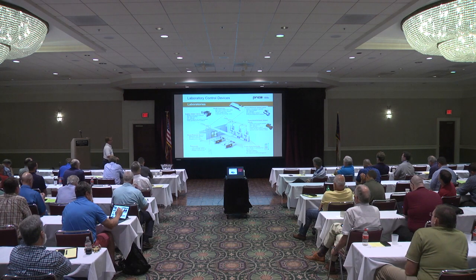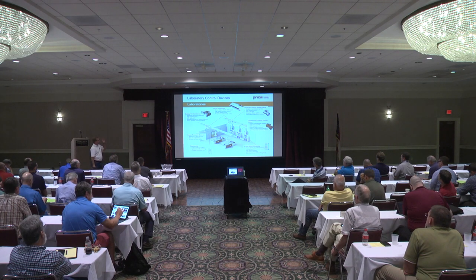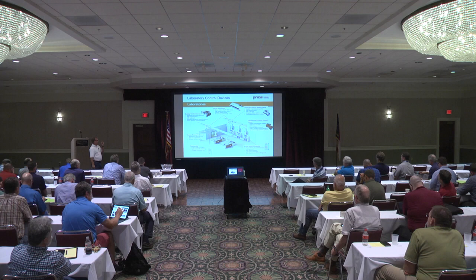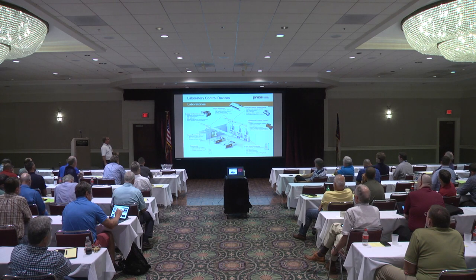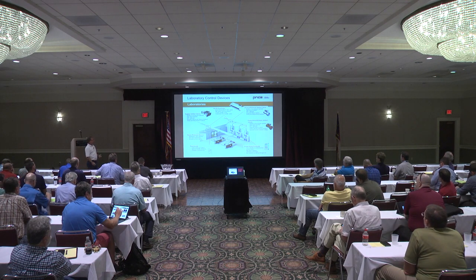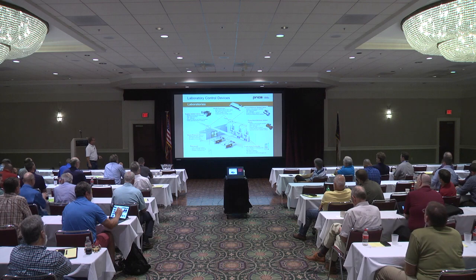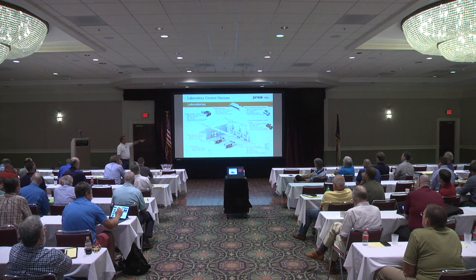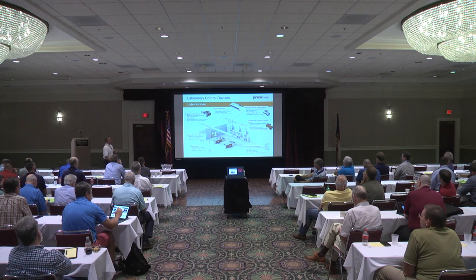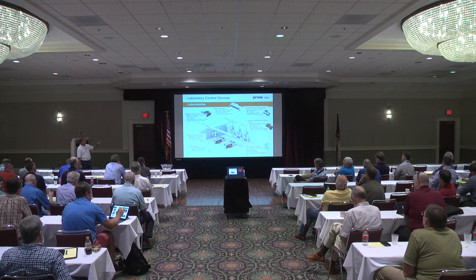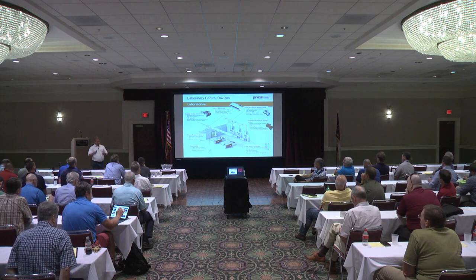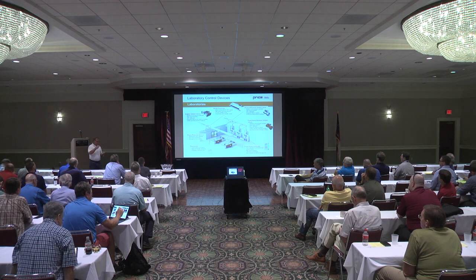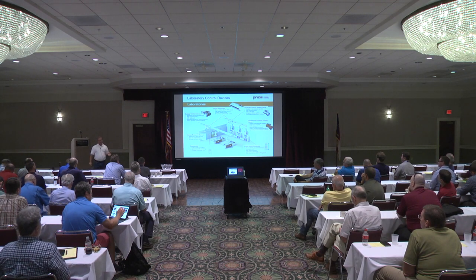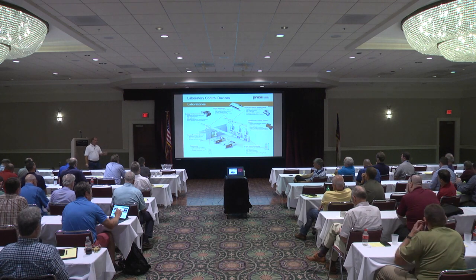So here's, I'll call it, a typical lab space. Fume hoods, temperature control, fume hood controller, room pressure sensor possibly. We're using Venturi valves in this setup. Again, Venturi valves for speed of response and accuracy of airflow and repeatability. In this space, there are three control things going on simultaneously in a lab environment all the time: fume hood containment, room pressure control, and temperature control. And that's all simultaneously happening all day, every day.